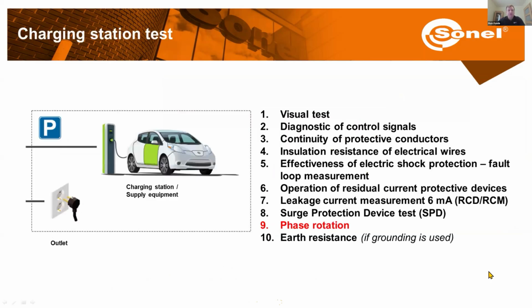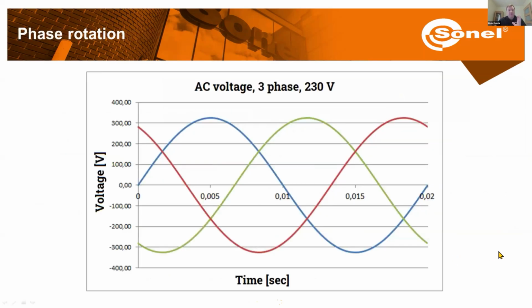Okay, then we have the next test, which is phase rotation. That's in case of three-phase AC charging stations, or in case of DC charging stations, but just their AC part. Here we just need to connect the test leads and make sure that the voltages for each phase are rotating in the right direction.